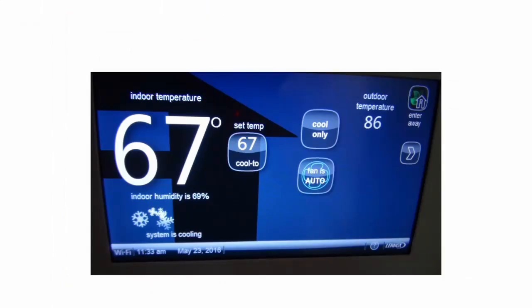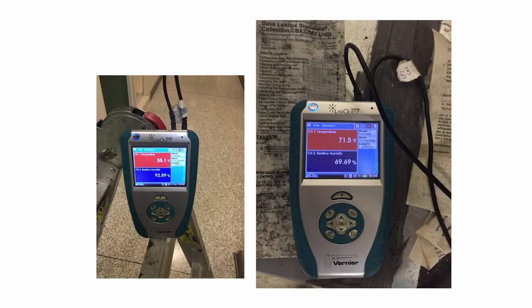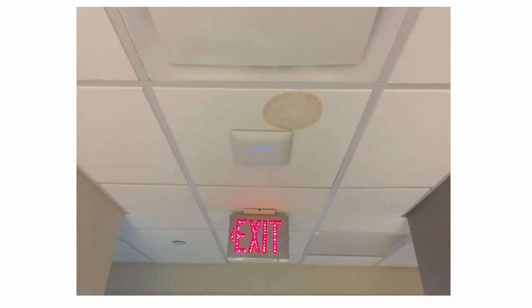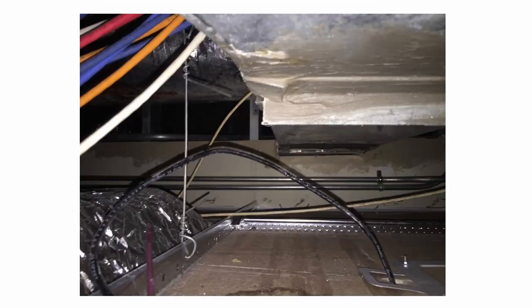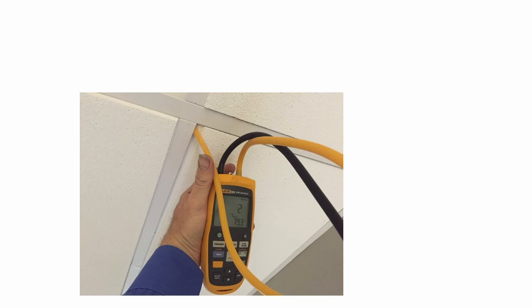The building was subsequently remodeled, and here is the new replaced thermostat. You can see the AHU blows saturated air and the humidity level is around 70%, which is when spontaneous microbial growth starts. The makeup air ducts are still leaking water that condensed inside them. The AC is cranked so low that water condenses on ducts and access panels, and the suspended ceiling remains negatively pressurized. It's disappointing when one considers that the very reason for the remodeling was to fix those issues.